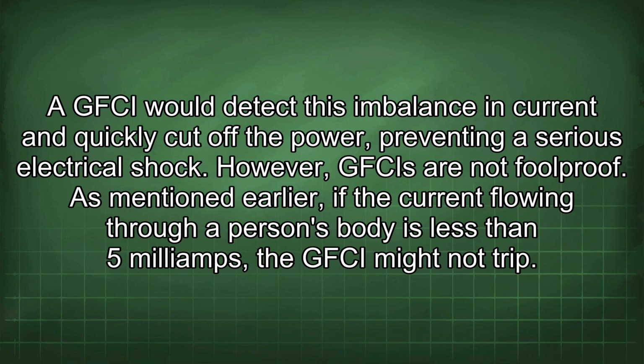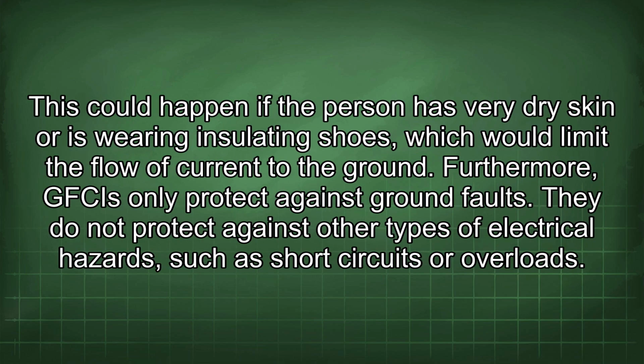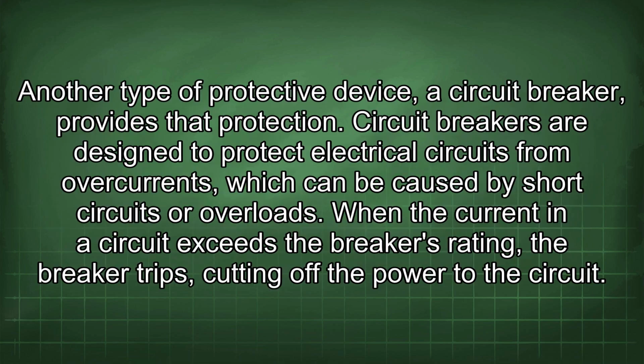However, GFCIs are not foolproof. As mentioned earlier, if the current flowing through a person's body is less than 5 mA, the GFCI might not trip. This could happen if the person has very dry skin or is wearing insulating shoes, which would limit the flow of current to the ground. Furthermore, GFCIs only protect against ground faults. They do not protect against other types of electrical hazards, such as short circuits or overloads. Another type of protective device, a circuit breaker, provides that protection.